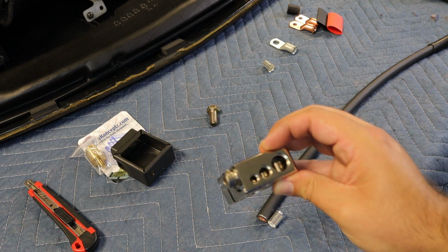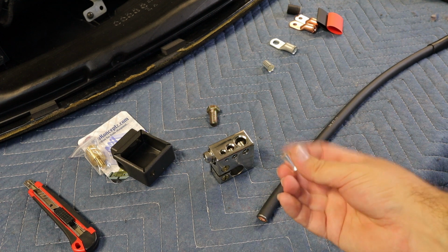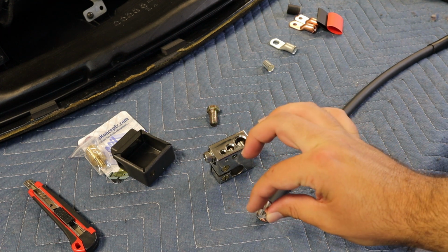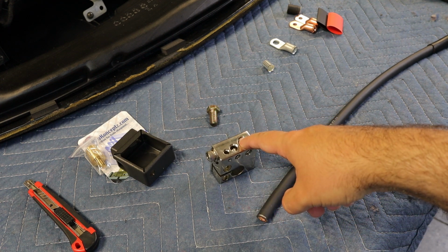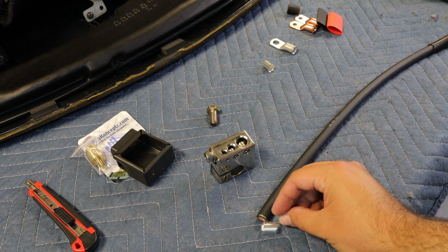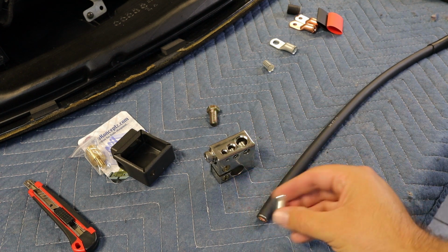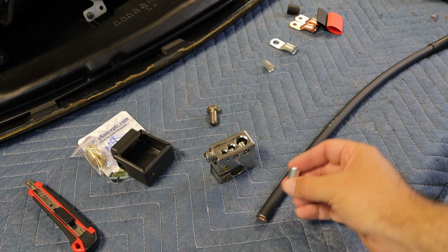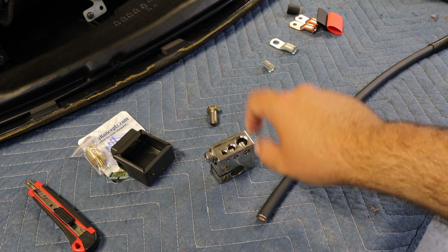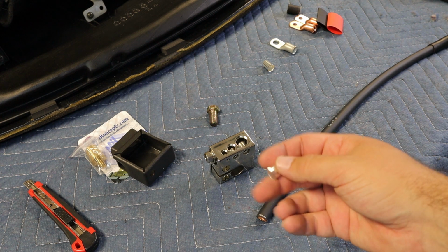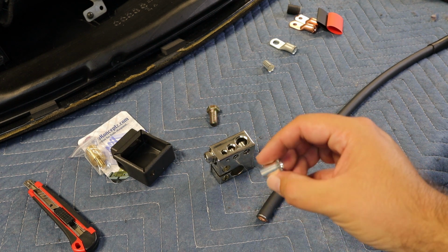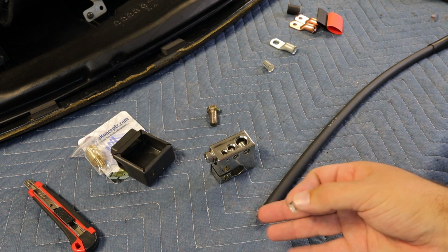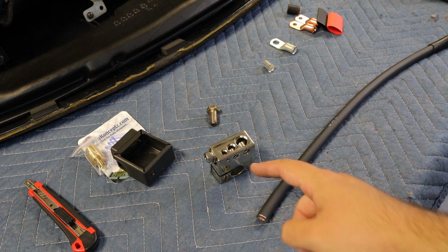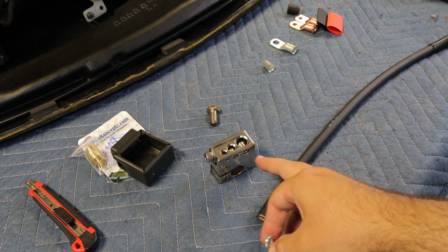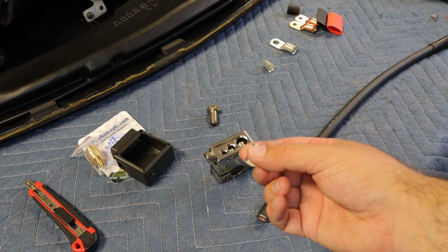To help with that issue, you want to put a wire ferrule over the wires before you set it in the set screw. Strip the sheathing off to the same dimension as the wire ferrule, then stick the ferrule in and tighten down the set screw. That deforms it so you can take the wire in and out and it'll always have that same shape, and the ferrule protects the individual copper wires from getting damaged.